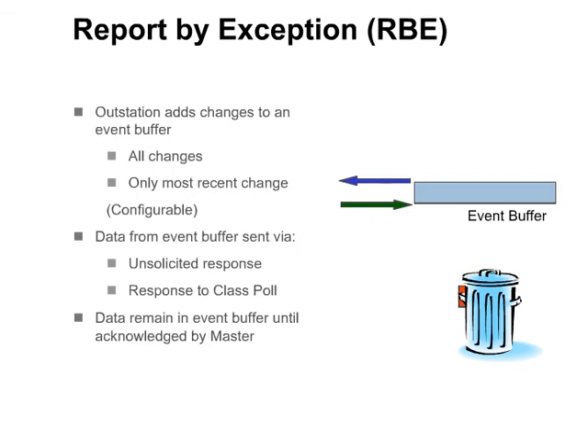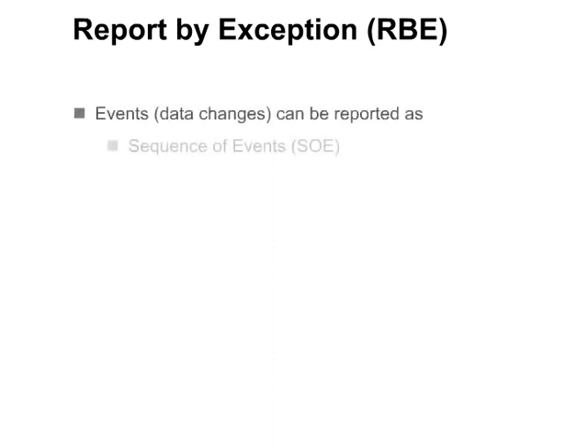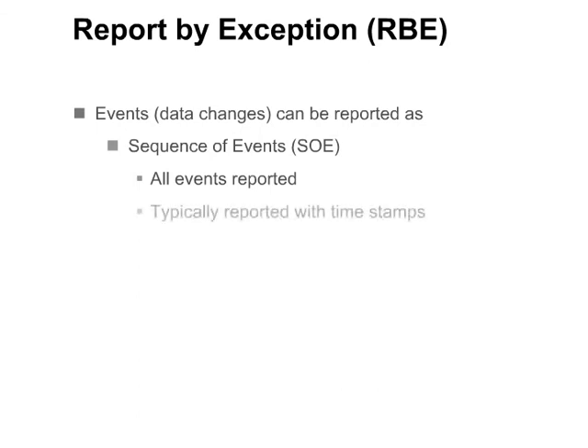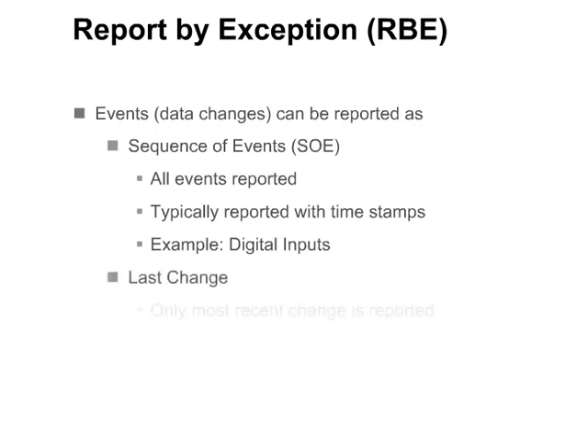Events, or data changes, can be reported either as a sequence of events or as only the last change. With sequence of events, all events are reported and they are typically reported with timestamps. Digital inputs are typically reported in this method. With last change, only the most recent change is reported and is typically reported with a variation without a timestamp. Analog inputs typically use the last change method.